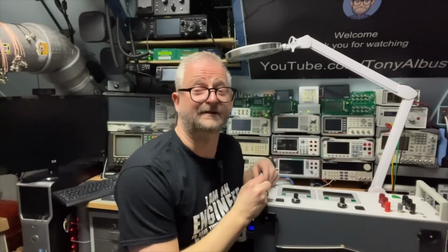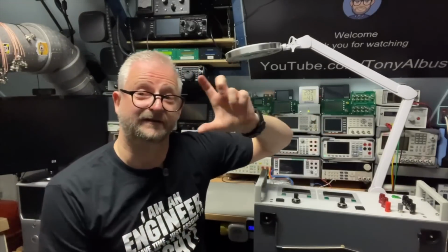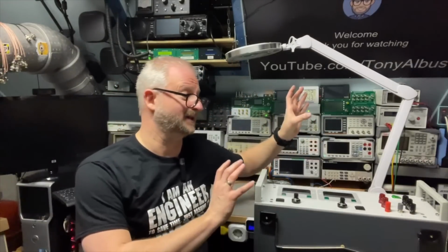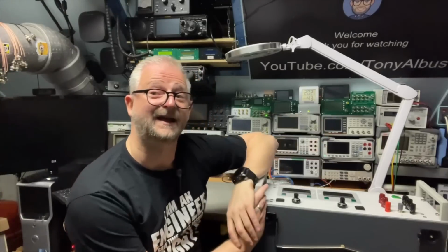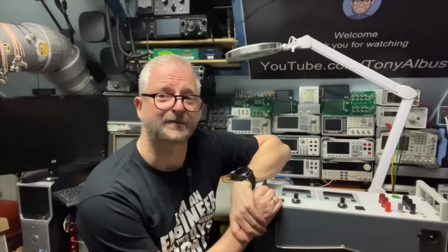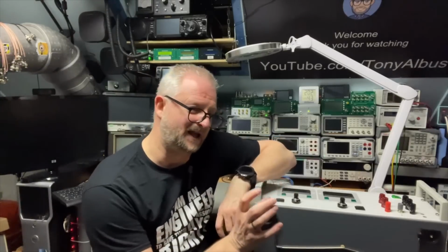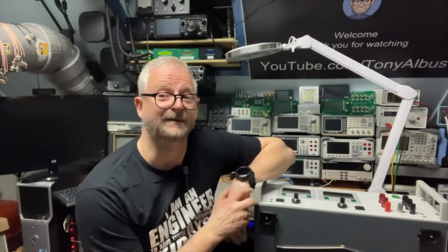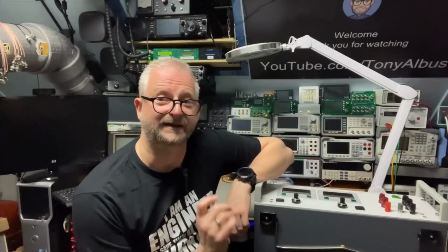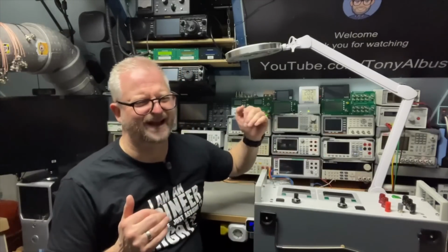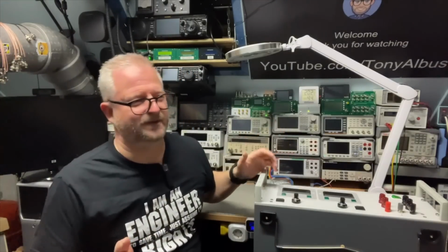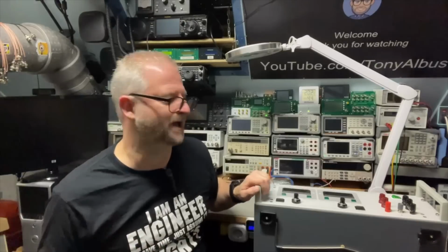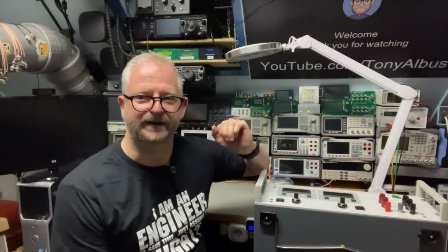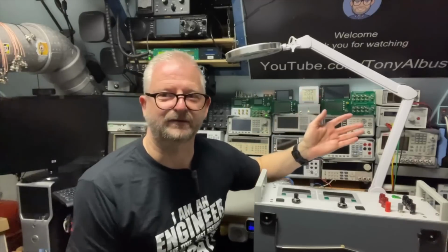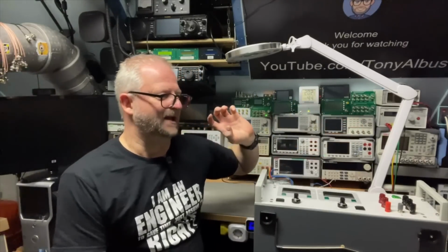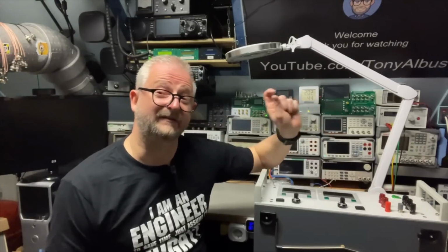Not only a separate group, I also used different fuses. Usually here in the Netherlands you use B characteristic with 16 amps per group, and your main fuses, at least in my house, were 25 amps with C characteristics. It's not completely comparable, but you get the idea, it's kind of a slow blow. So instead of allowing 3 times the current like the B characteristic, it allows maybe 10 times, but very, very short.